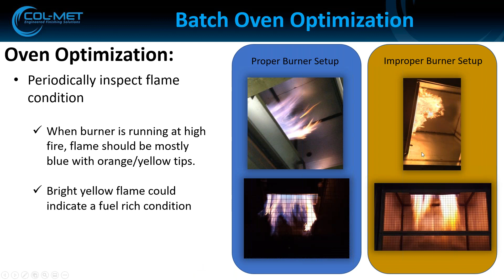So if the flame looks bright and yellow like what we saw previously, it typically means that you don't have the proper air to fuel ratio. And normally that means that it's not getting enough air, because the gas is pretty much preset. It just modulates the gas up and down.